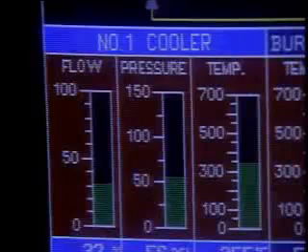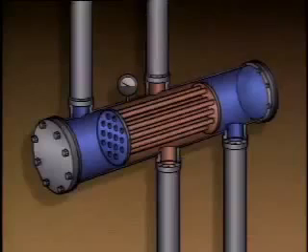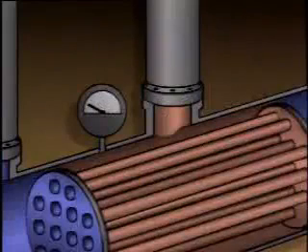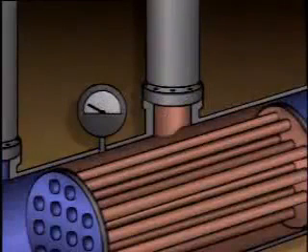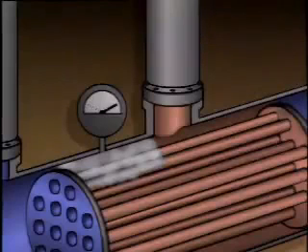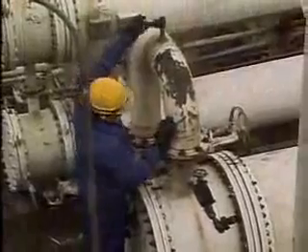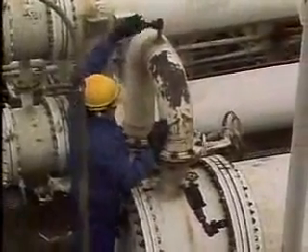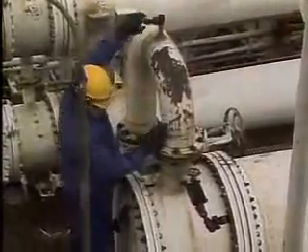There are also situations where the pressure inside a heat exchanger may be affected. For example, this can occur in heat exchangers that are used to condense process vapors. In this situation, non-condensable gases partially fill the unit, reducing the amount of heat transfer area that the process vapor can come in contact with. In turn, this reduces the amount of vapor that can be condensed. The flow of vapor will start to decrease, and the pressure inside the unit will start to increase. Regardless of how gases get into the heat exchanger, the unit must be vented to allow them to escape. Repeated venting may be necessary to ensure that the heat exchanger remains free of air and other undesirable gases.